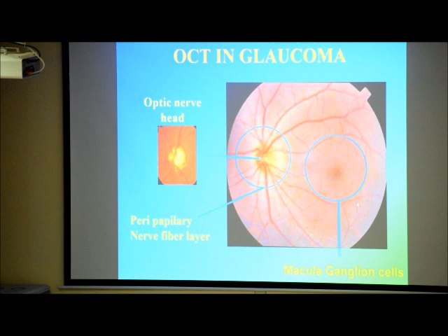Zone 1 is the patient detail and the test details, and zone 2 is the image quality, that is indicated by the signal strength. The signal strength of the OCT machine should be more than 6. Below 6 signal strength should not be interpreted, and the highest signal strength is up to 10. So above 6 signal strength, the printout should be interpreted.